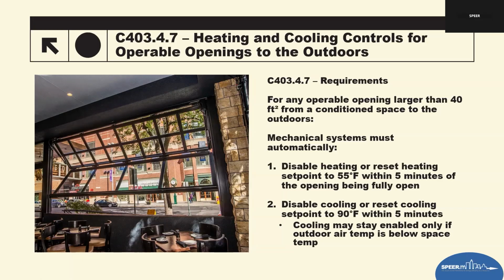So plan review tips: look for clear HVAC interlock sequences in the control narrative. Identify the operable openings. Are they greater than 40 square feet? If they are on the plans, then you need to find where it's tied into the HVAC system, or it meets one of these exceptions that are listed as impractical or unnecessary, or the code official has made that call. Confirm the set point reset values of 55 degrees and 90 degrees appear on the programming documents.